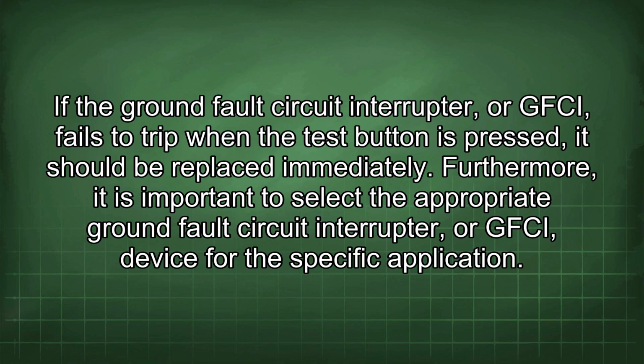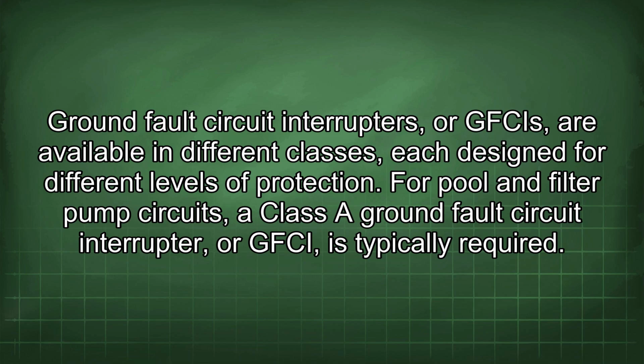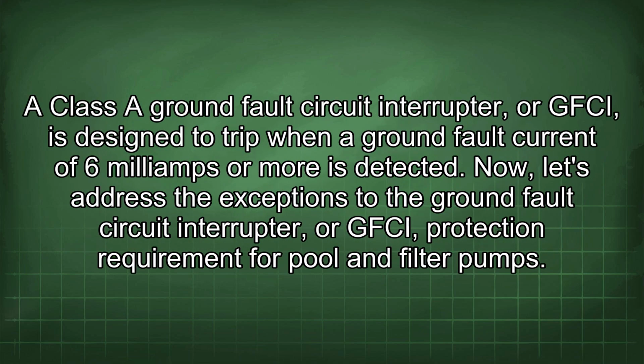Furthermore, it is important to select the appropriate GFCI device for the specific application. GFCIs are available in different classes, each designed for different levels of protection. For pool and filter pump circuits, a class A GFCI is typically required. A class A GFCI is designed to trip when a ground fault current of 6 mA or more is detected.